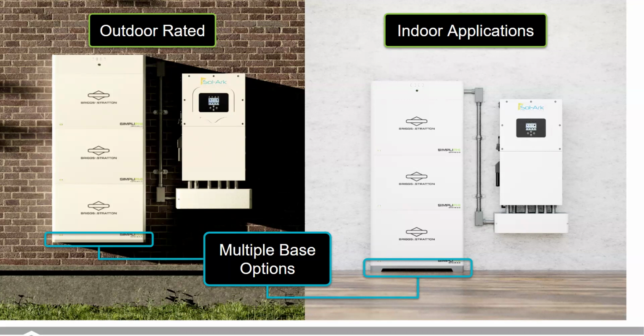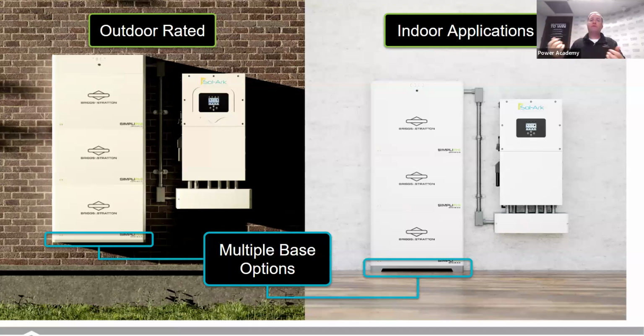Jean-Pierre asks if the batteries get underwater, will it still work? How does water intrusion get handled through the stackable units, and what do we know about our outdoor rating? The batteries are IP65, which I don't believe is full submersion. We get this sometimes when we go down to Florida or other places where there's flood zones, and by code you have to have these things up 8 feet on the wall. Then it makes me wonder, are there other conflicting codes when you have stuff that high up, since you can't necessarily work on it. I will say these batteries do not work underwater. I would imagine that if they do get submerged, the battery management systems and protections in the batteries would potentially detect the short and shut themselves off. But yeah, IP65 as well.